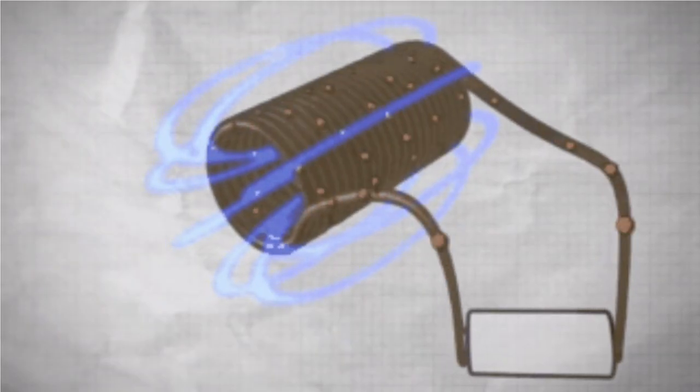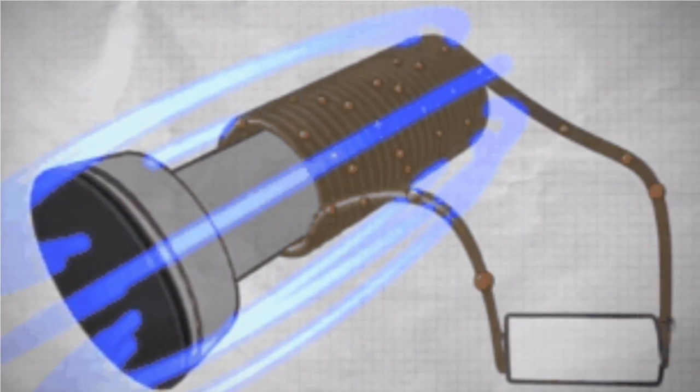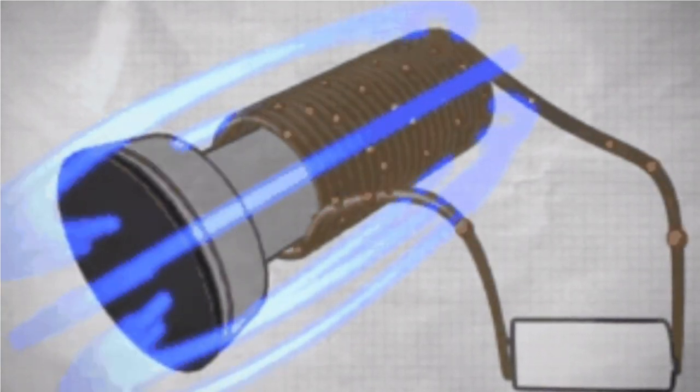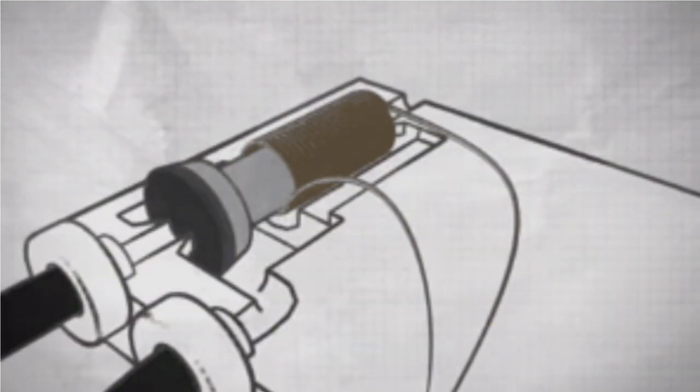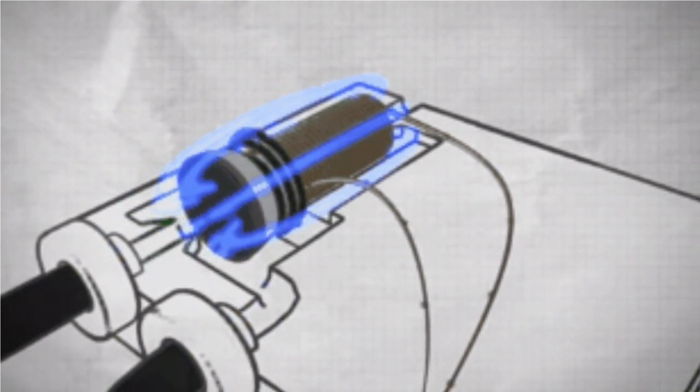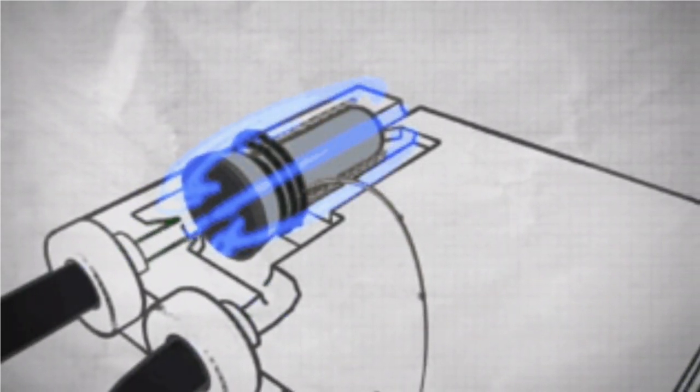First of all, find a 24 volts power source and connect it to the coil. If any noise is heard it means the solenoid valve coil and valve element are normal, which can ensure normal connection.